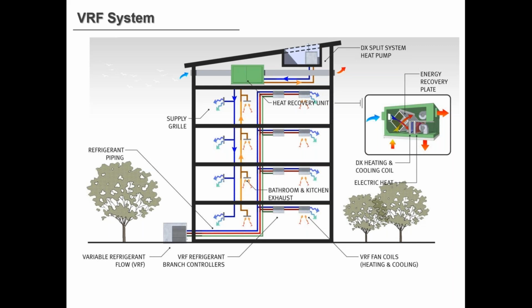So this is sort of a section of what that could look like within the VRF component of what we did. I don't know if you can see my arrow here, but what we have here is a dedicated ventilation air system with energy recovery, and that provides ventilation air to the new components of the building. Let's call it all the classrooms. And then decoupled from that is a variable refrigerant flow, or a VRF system, that does the heating and cooling.